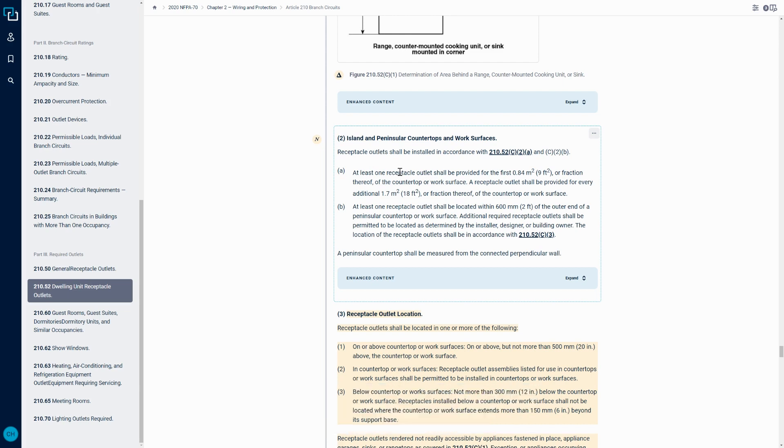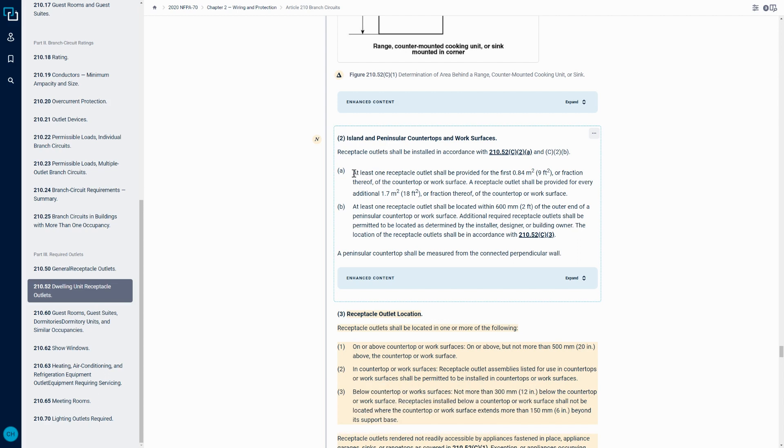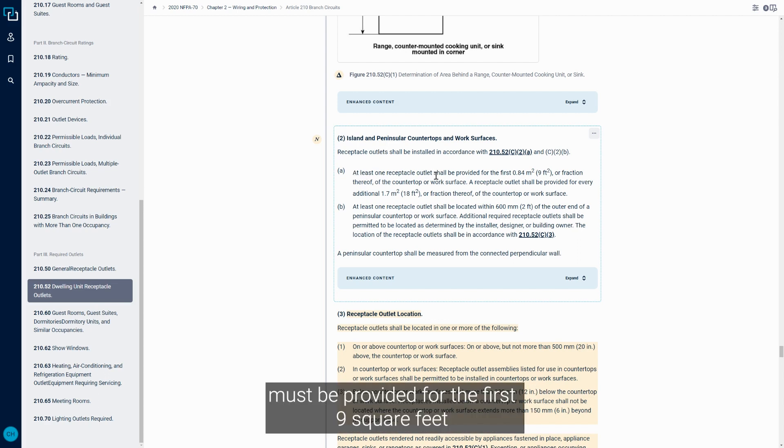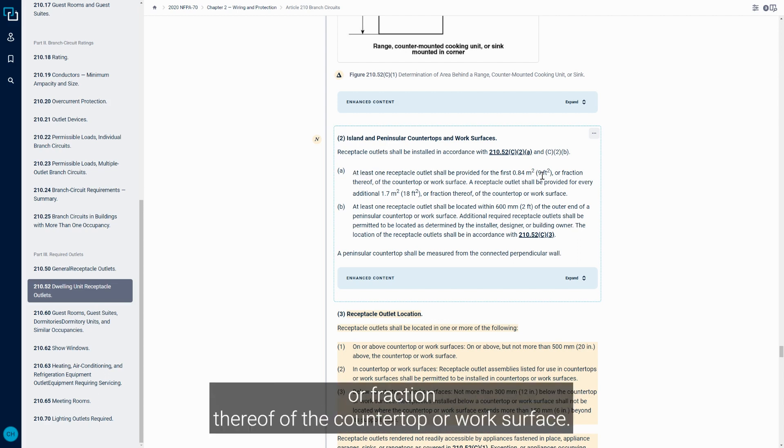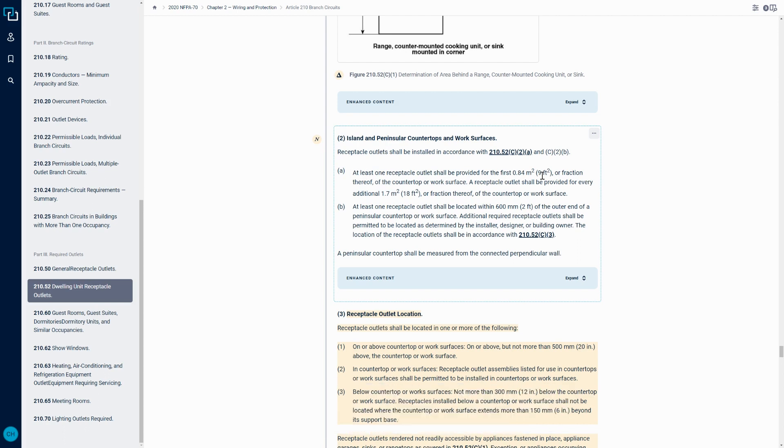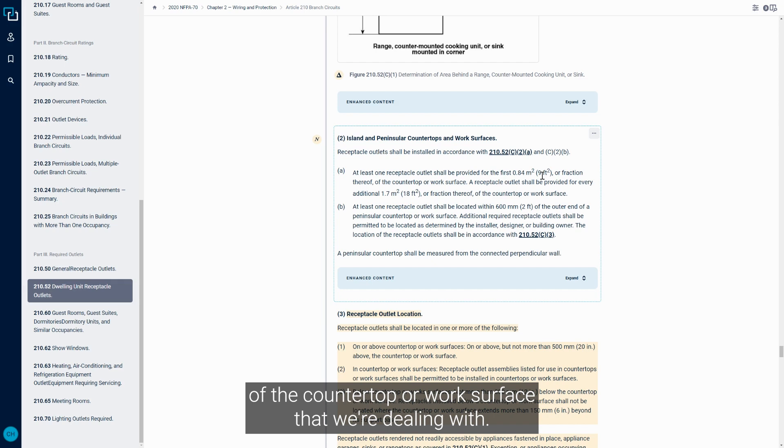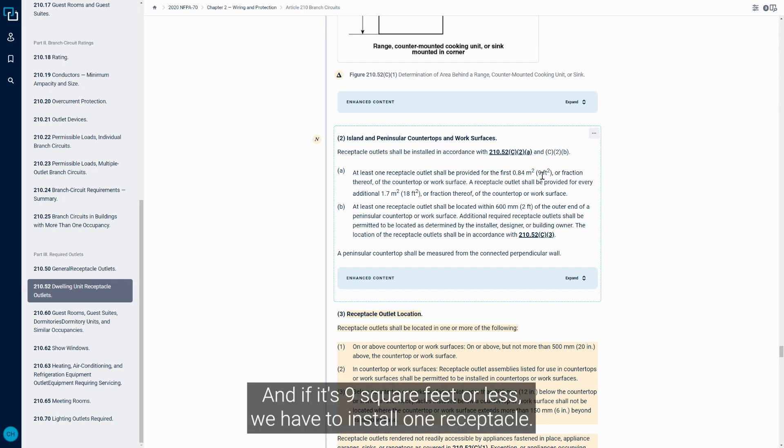So the first rule is that at least one receptacle must be provided for the first nine square feet or fraction thereof of the countertop or work surface. So we're measuring the overall square footage of the countertop or work surface that we're dealing with, and if it's nine square feet or less we have to install one receptacle.